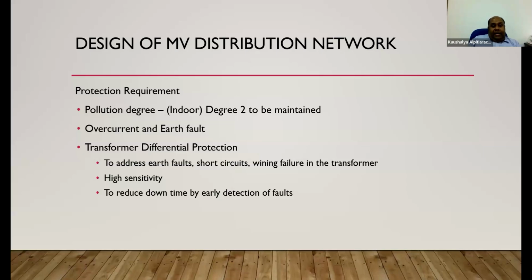And differential protection is very sensitive and can address faults quickly, ranging from earth faults to short circuits, winding failure in the transformers, and so on. And that can reduce your downtime by early detecting your faults. If you have a harmonic environment in your low voltage side, better to implement transformer differential protection. Apart from that, you should have restricted earth fault. That is, of course, from your low voltage winding towards your LV panel board. So I'm not discussing those stuff during this presentation.